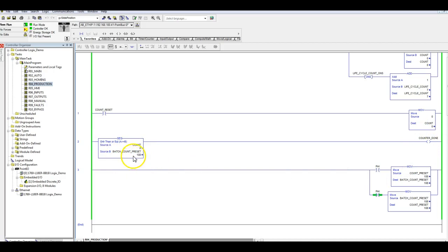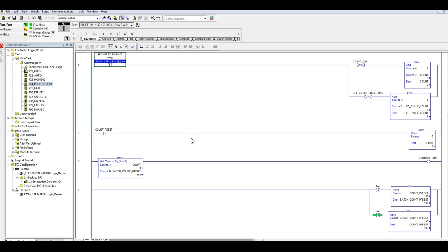If my count is greater than 100 I will have a counter done. I can have this set through my HMI and change to any preset that I want. That's real important. In my cycle every operator may need to get 100 parts done in a two-hour period. They don't have to pay attention to the count, they'll wait for the indicator on the HMI to give them a message that the cycle count is done.